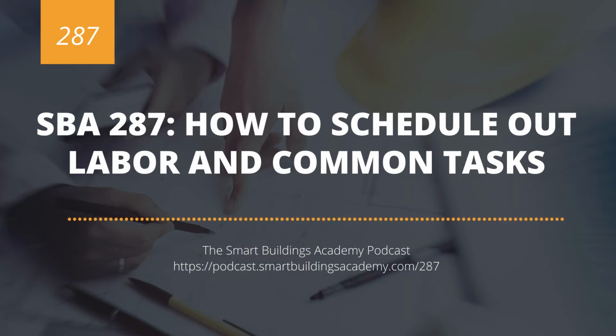So we're looking at how we schedule out this labor and these common tasks. Well, we have to understand how our team is structured. A typical structure for a team will be a startup technician who will be responsible for point-to-point checkout, uploading and downloading controllers, downloading graphics, and doing basic setup of the system. We have a designer who can be split into potentially 2 roles.